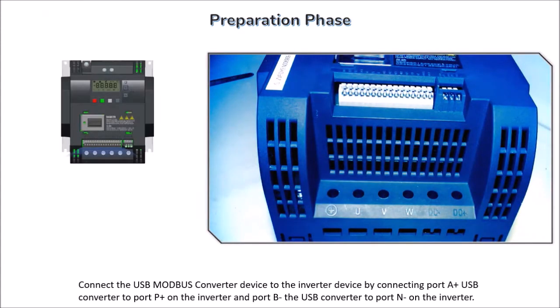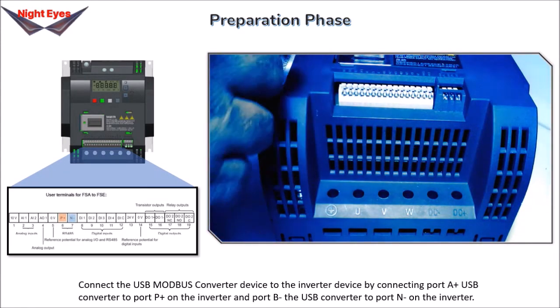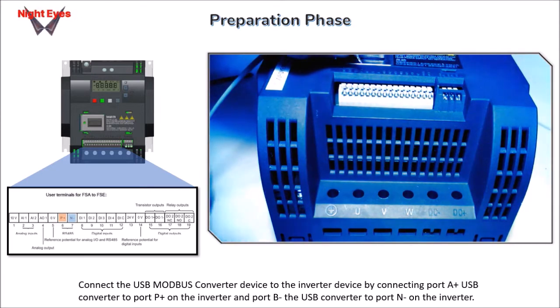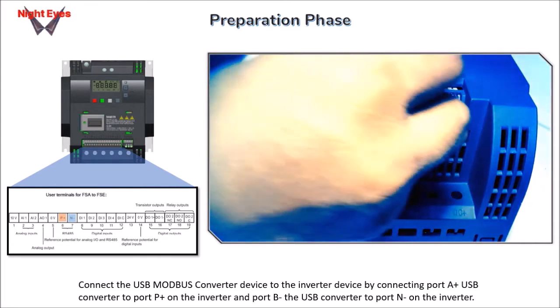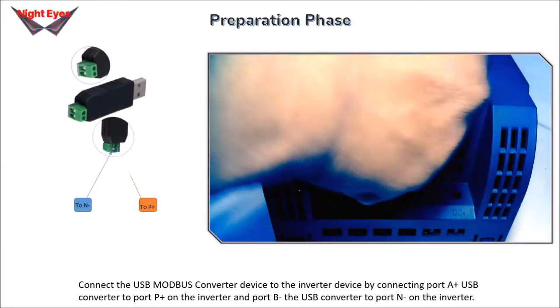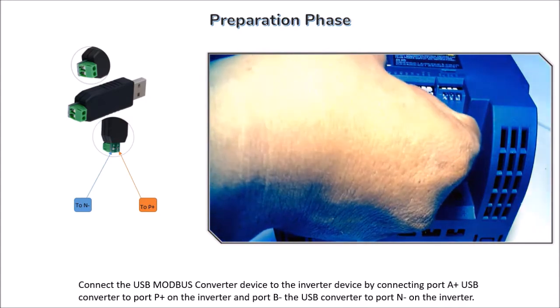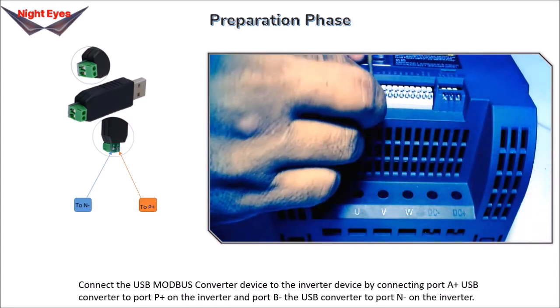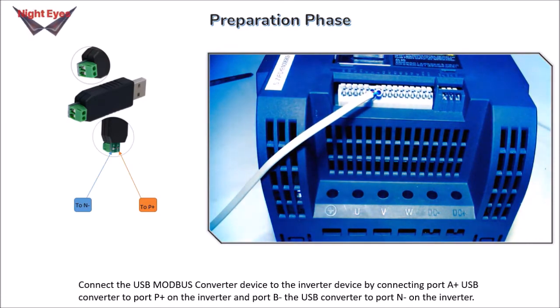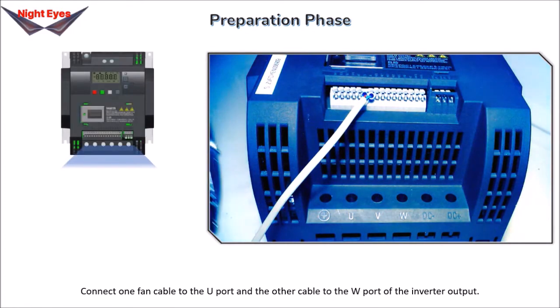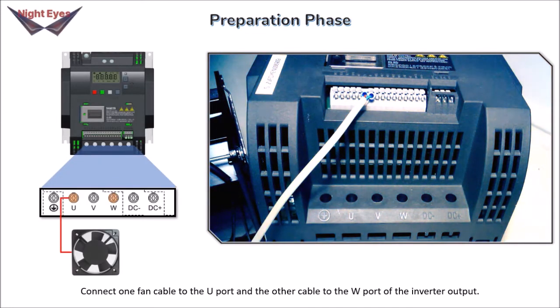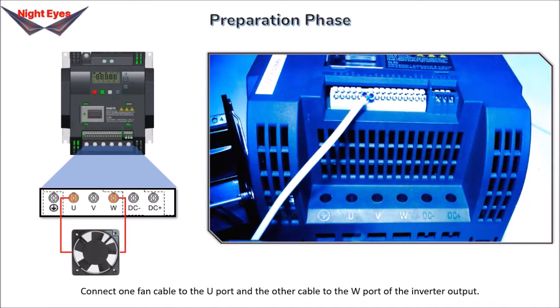The preparatory steps are: connect the USB Modbus Converter device to the inverter by connecting port A+ of the USB converter to port P+ on the inverter, and port B- of the USB converter to port N- on the inverter. Connect one fan cable to the U-port and the other cable to the W-port of the inverter output.